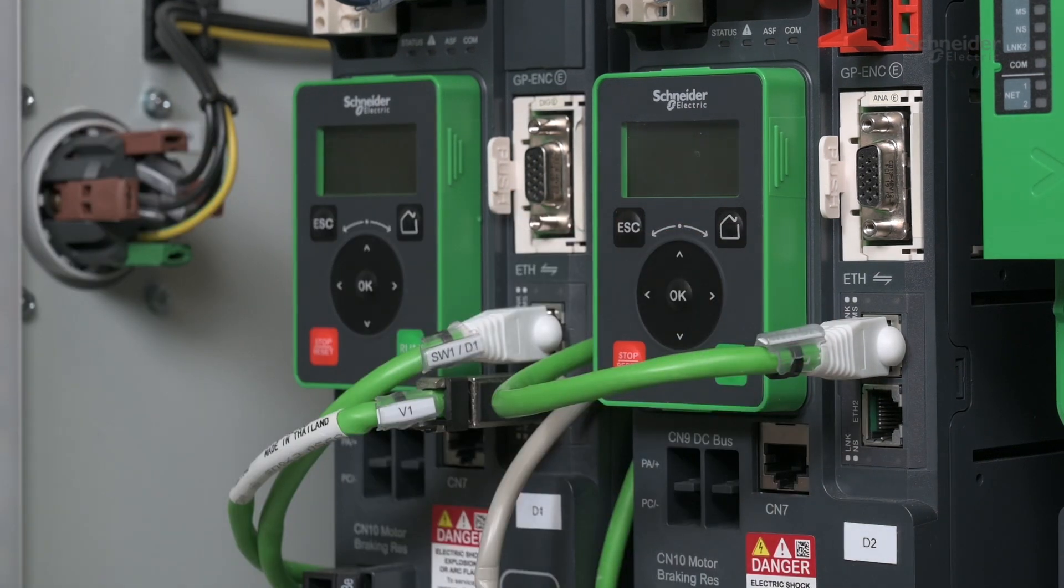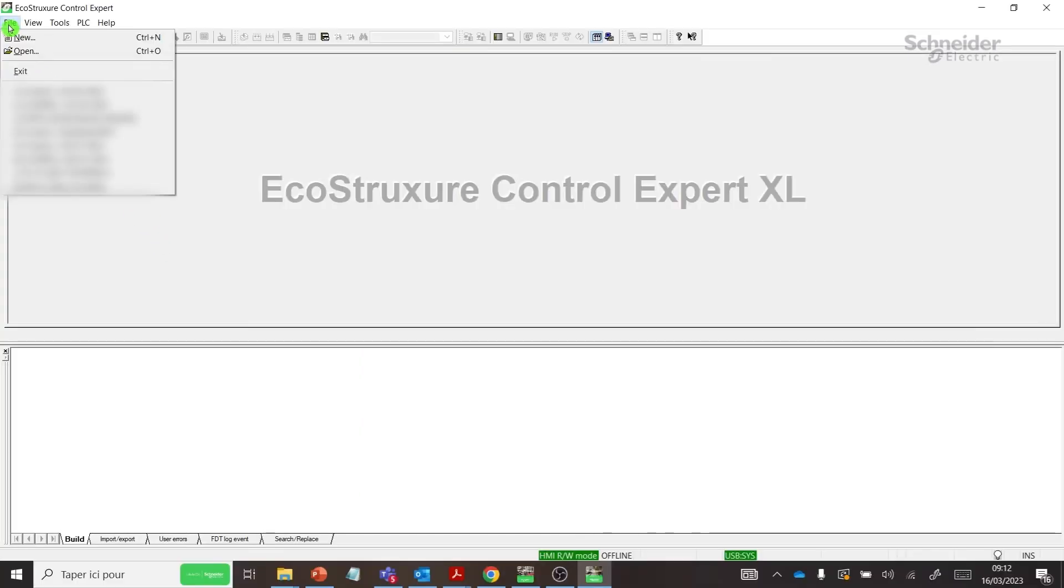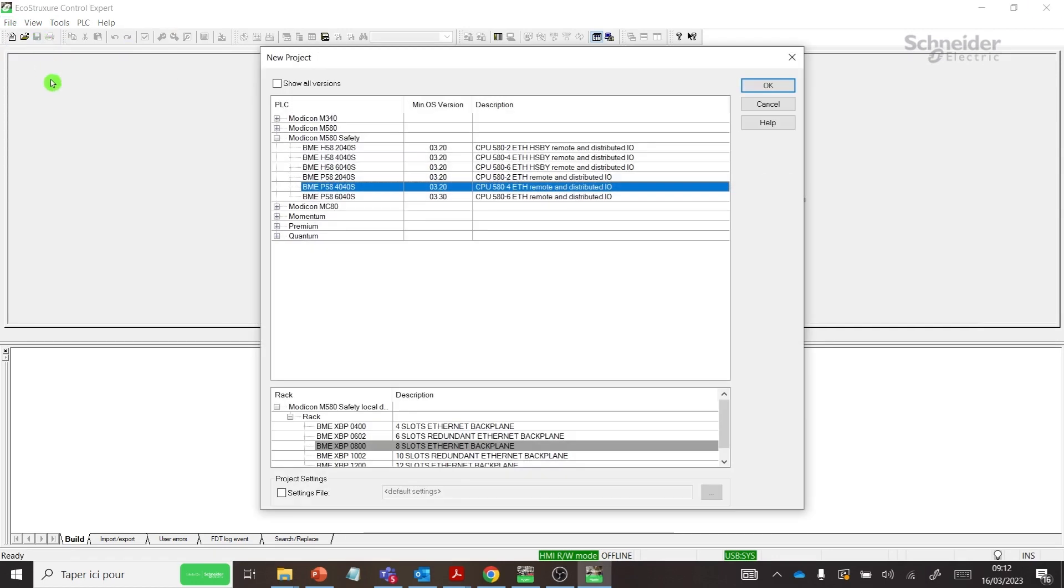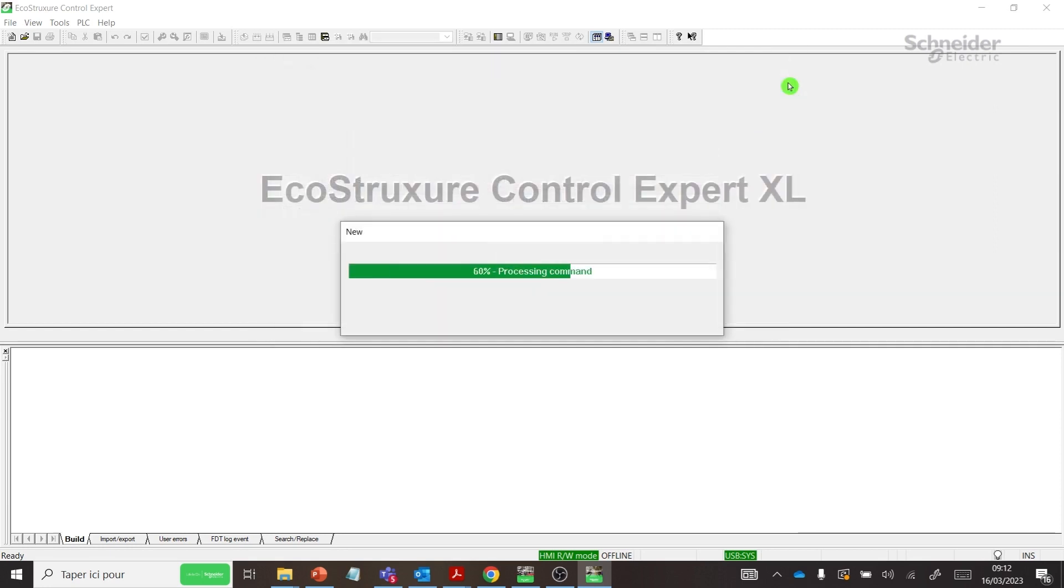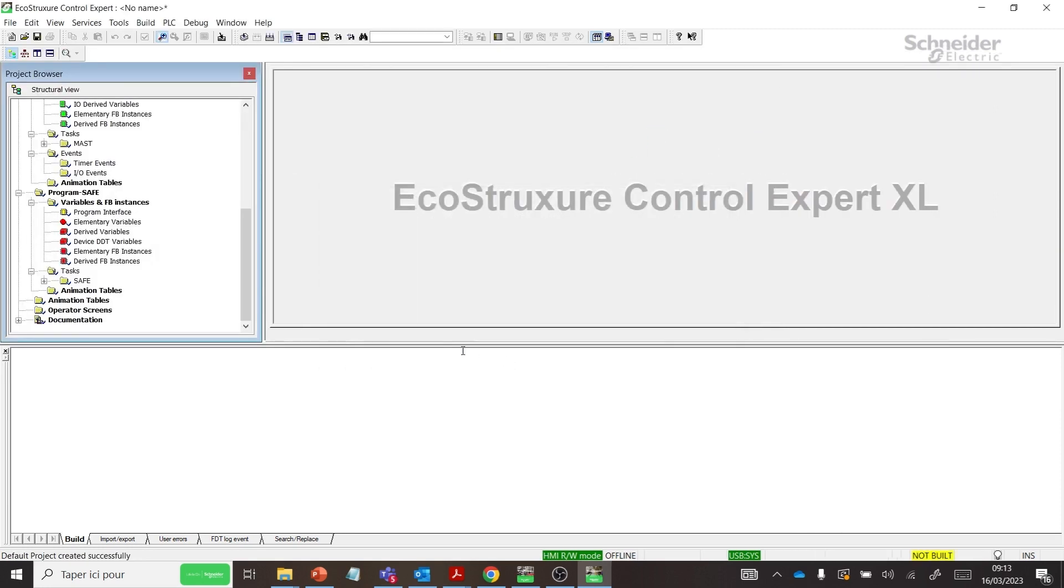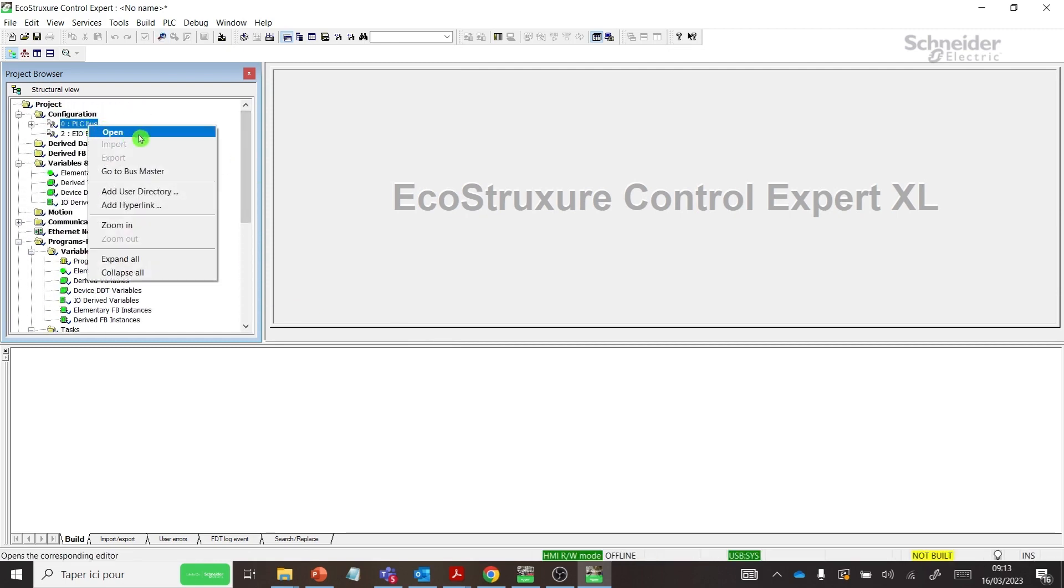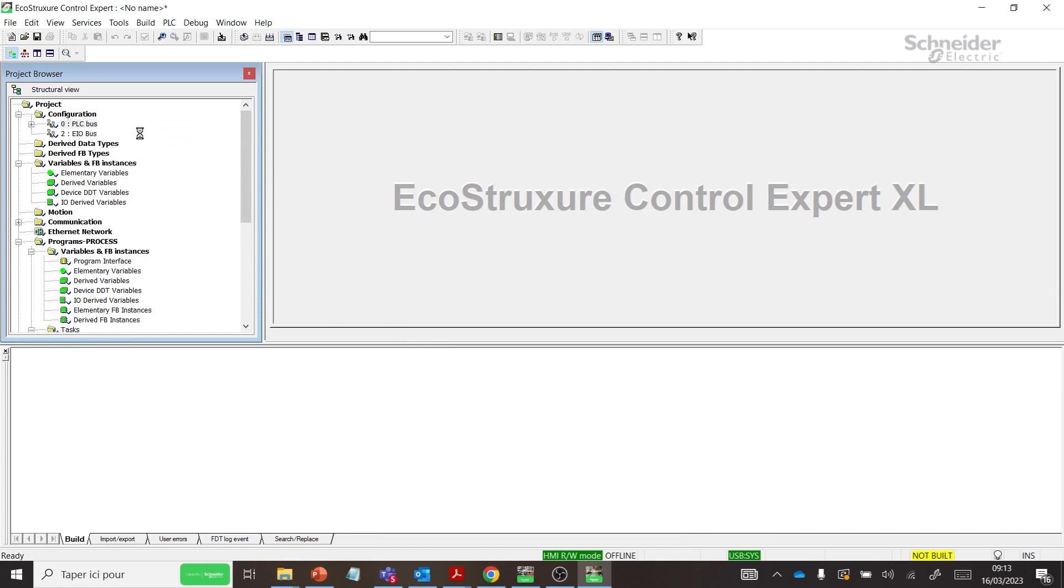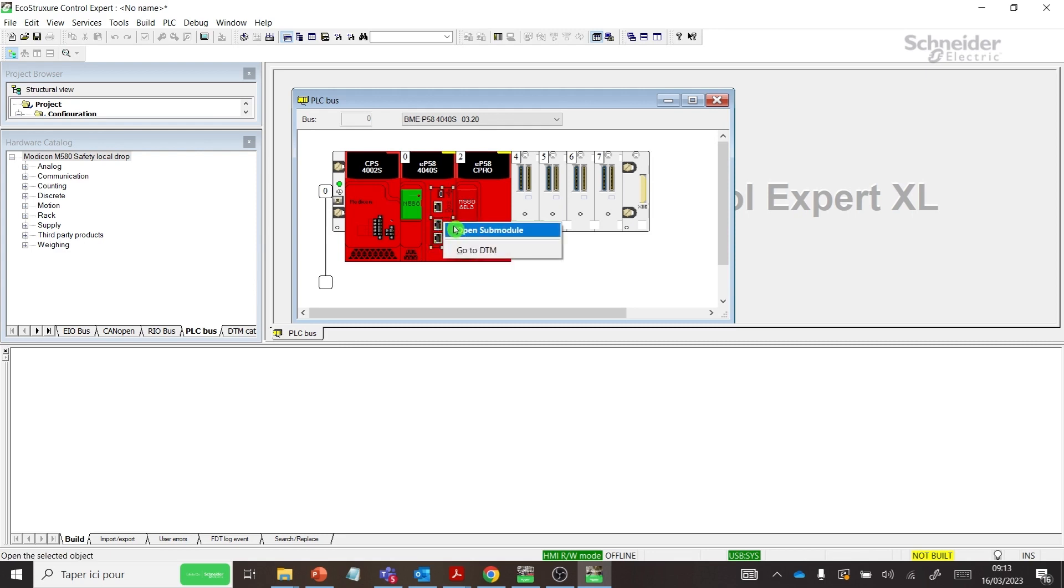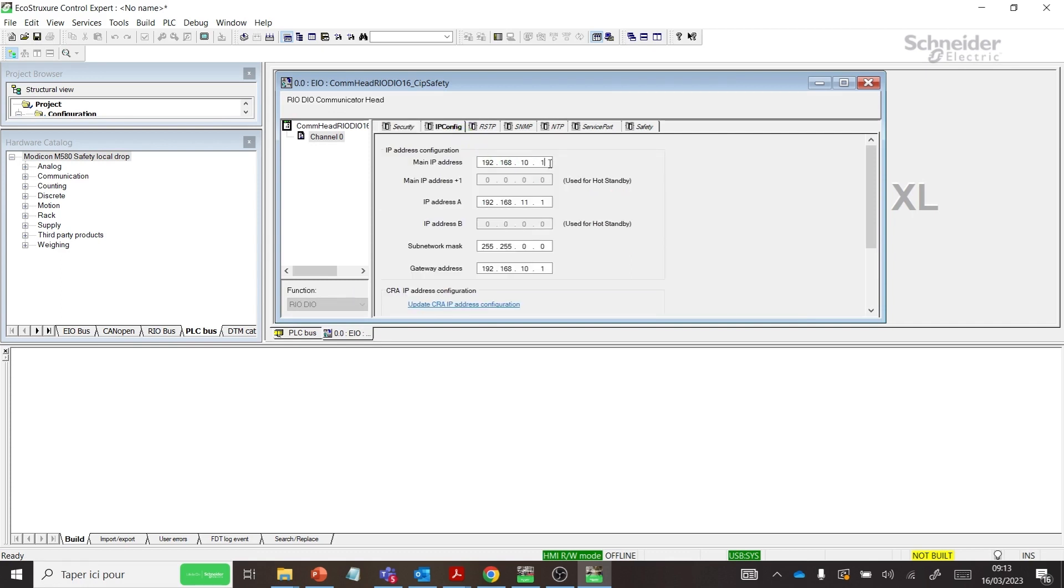Here is the commissioning procedure for Safety Drive integration through EcoStruxure Control Expert. Step 1: Configure IP address for M580 Safety PLC. Open EcoStruxure Control Expert. Create a new project with M580 Safety System with application password. Create a password for your project. Refer to the M580 Safety Manual. Open the PLC bus configuration. Right-click on Open Submodule. Configure M580 PLC IP address.